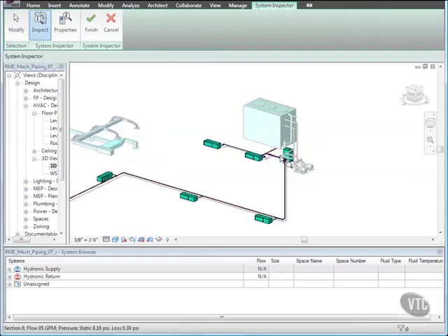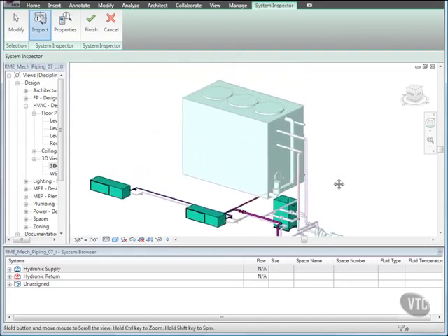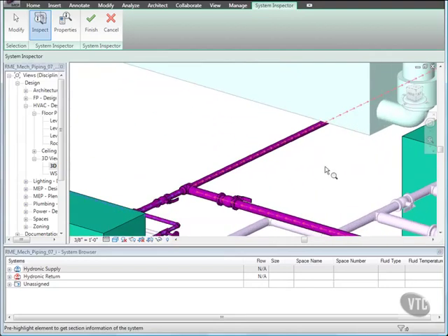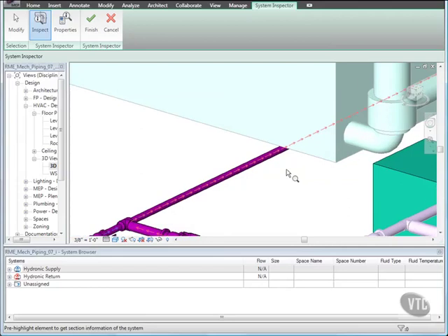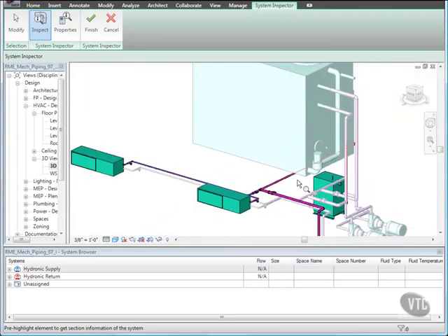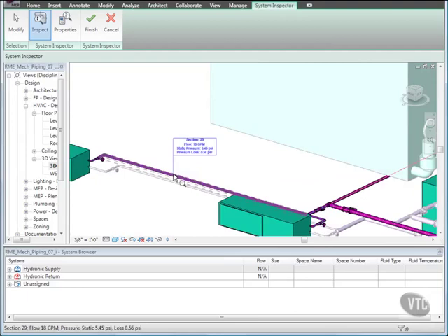When you do, arrows display on the pipe indicating the flow direction for both the main and the branches in the pipe system. The critical flow, indicated by red arrows, is in the main line going to the boiler. Now place the cursor over the same section of return piping. When you do, an inspection flag reports the section number, flow, and pressure information, including pressure loss. This information helps you modify the system design as required.